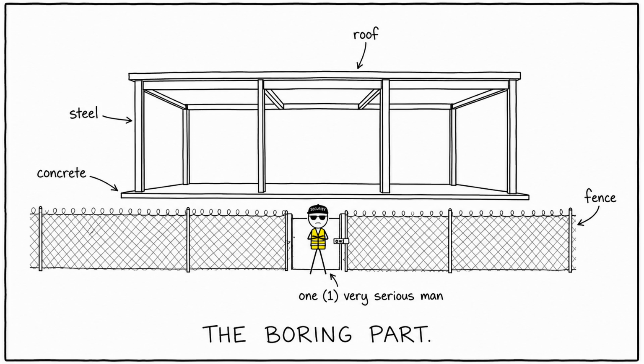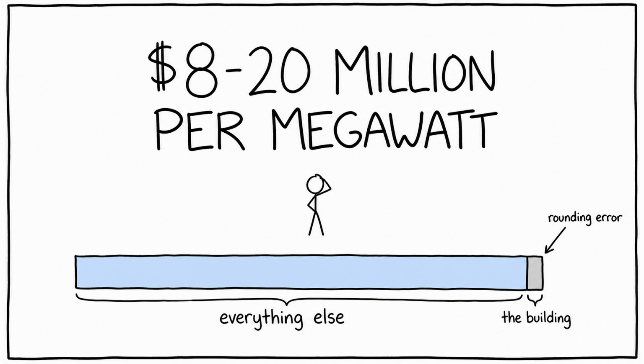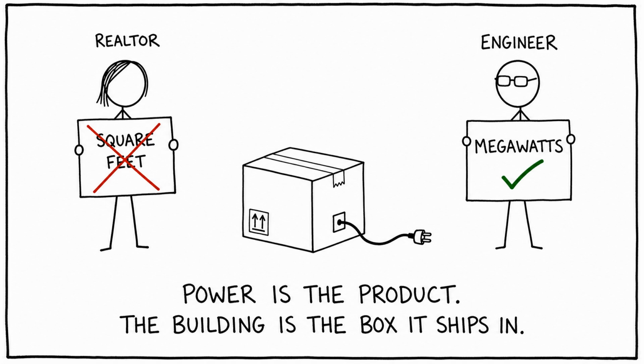Let's get the boring part out of the way first: the shell. A concrete slab, some steel, a roof, a fence, and one very serious man at the gate. A modern facility runs about $8 to $20 million per megawatt to build. That sounds enormous, but the actual building is a rounding error inside that number. Here's the trick to understanding data centers: nobody measures them in square feet, they measure them in megawatts. Power is the product. The building is just the box it ships in.